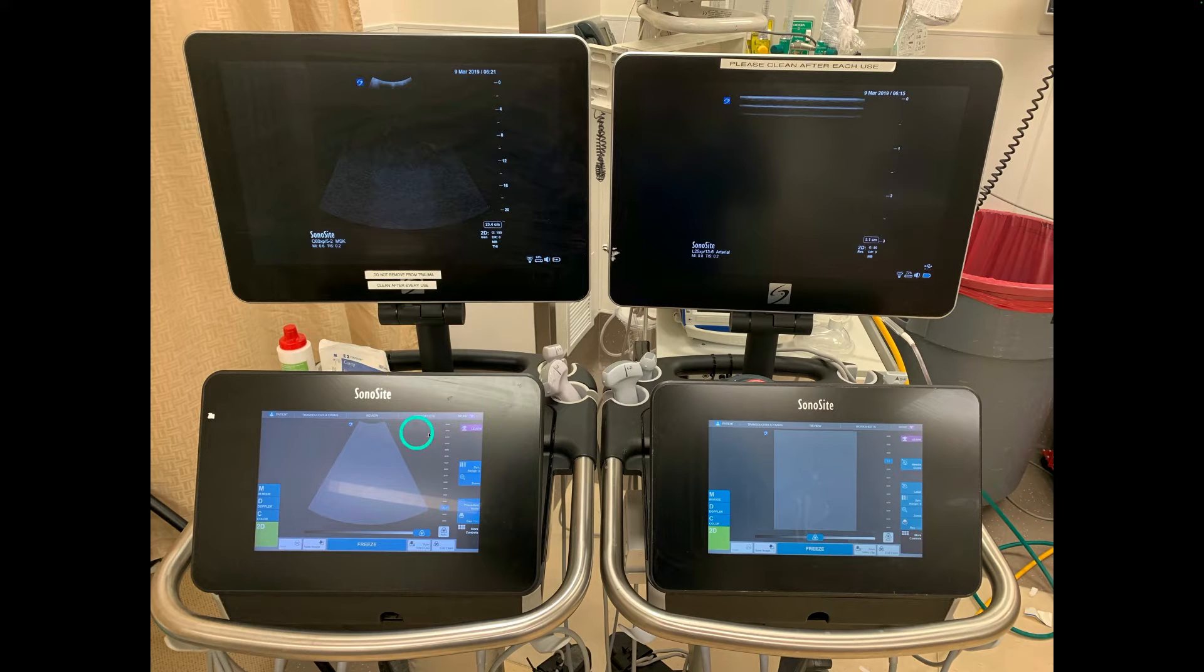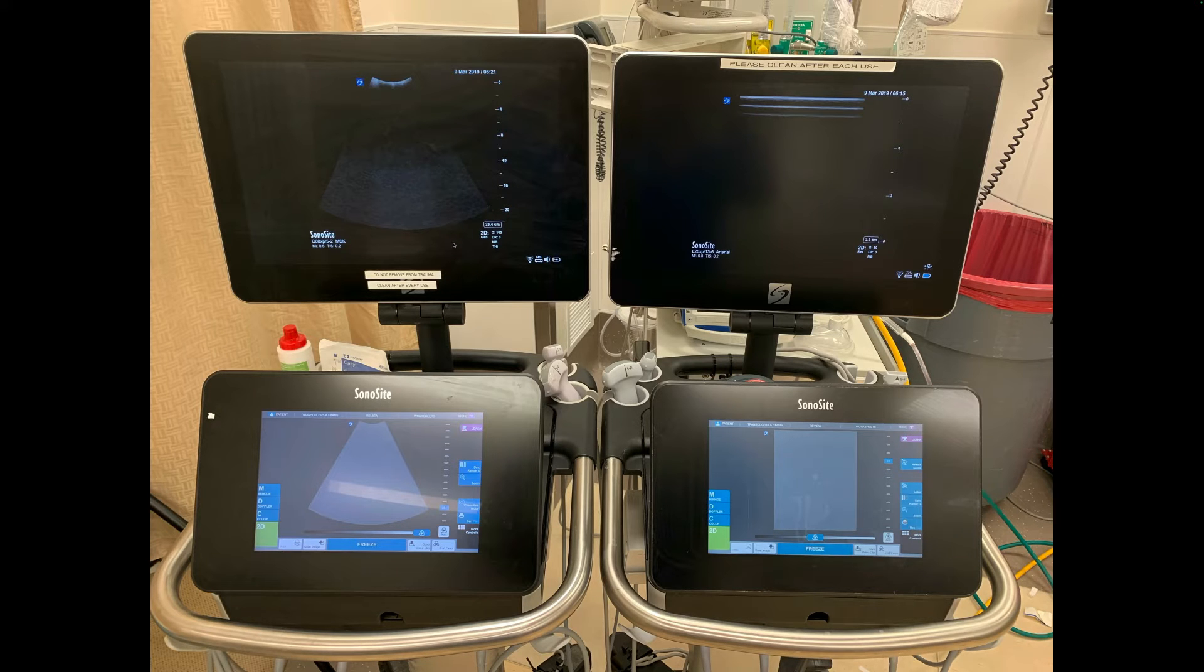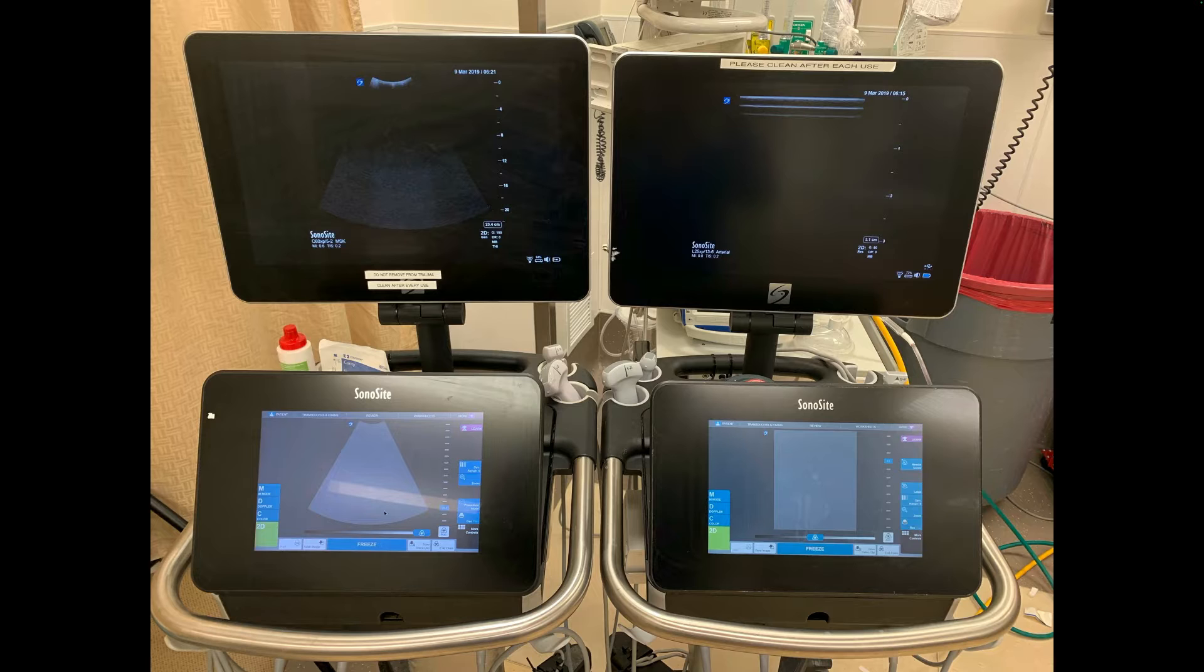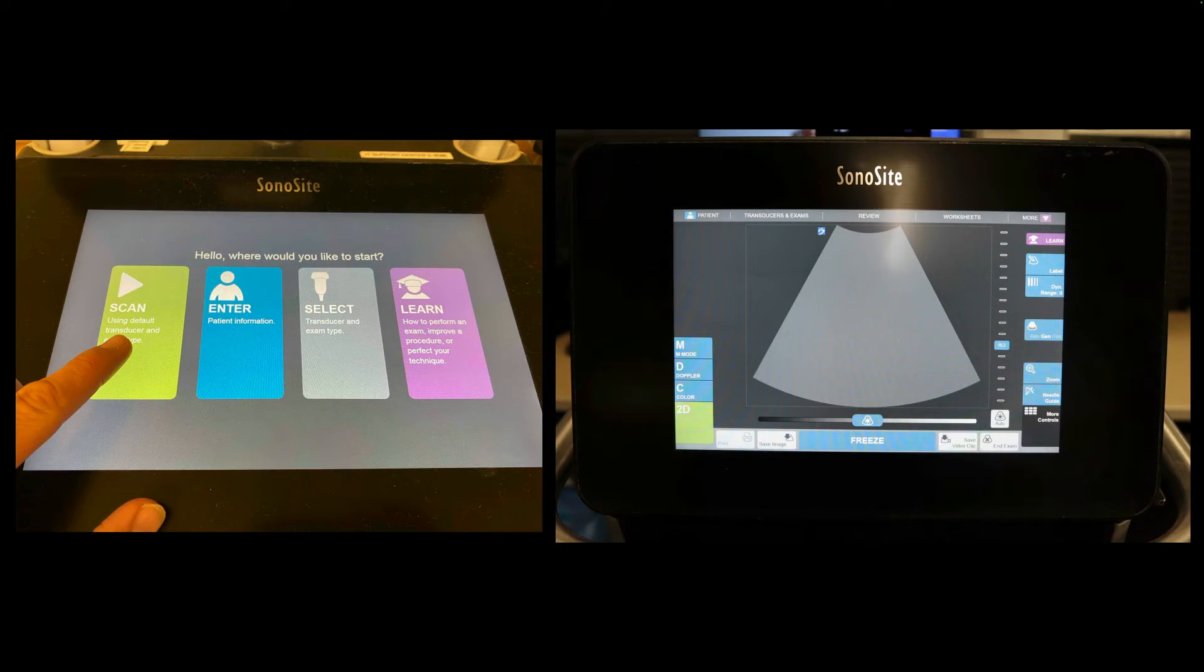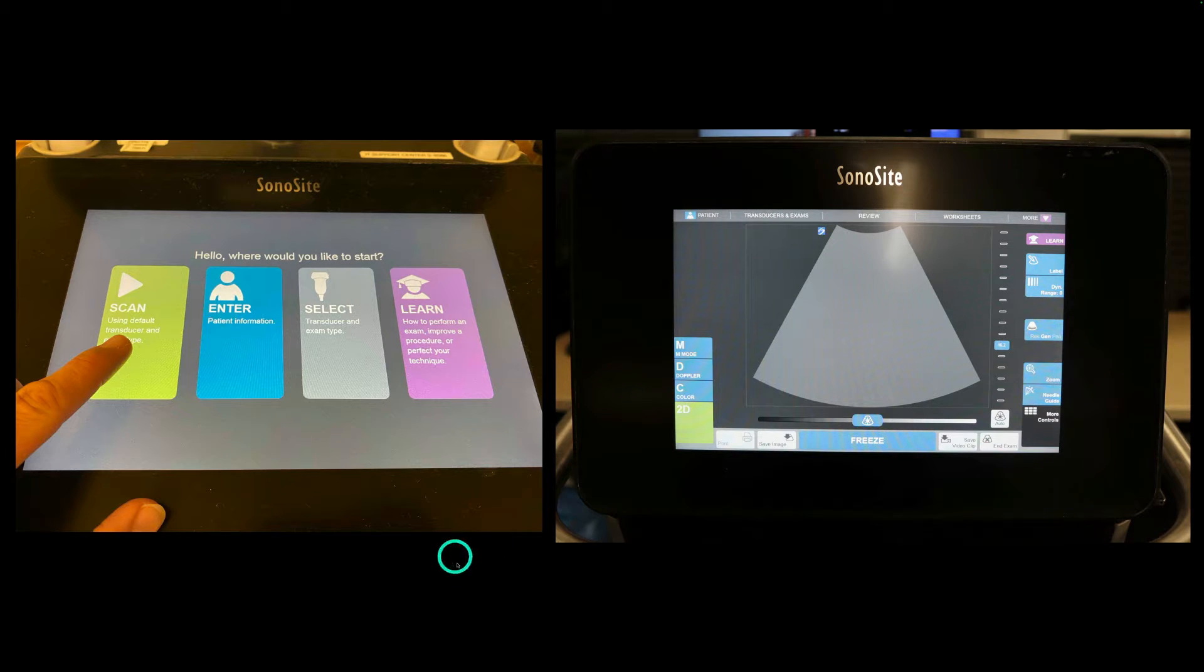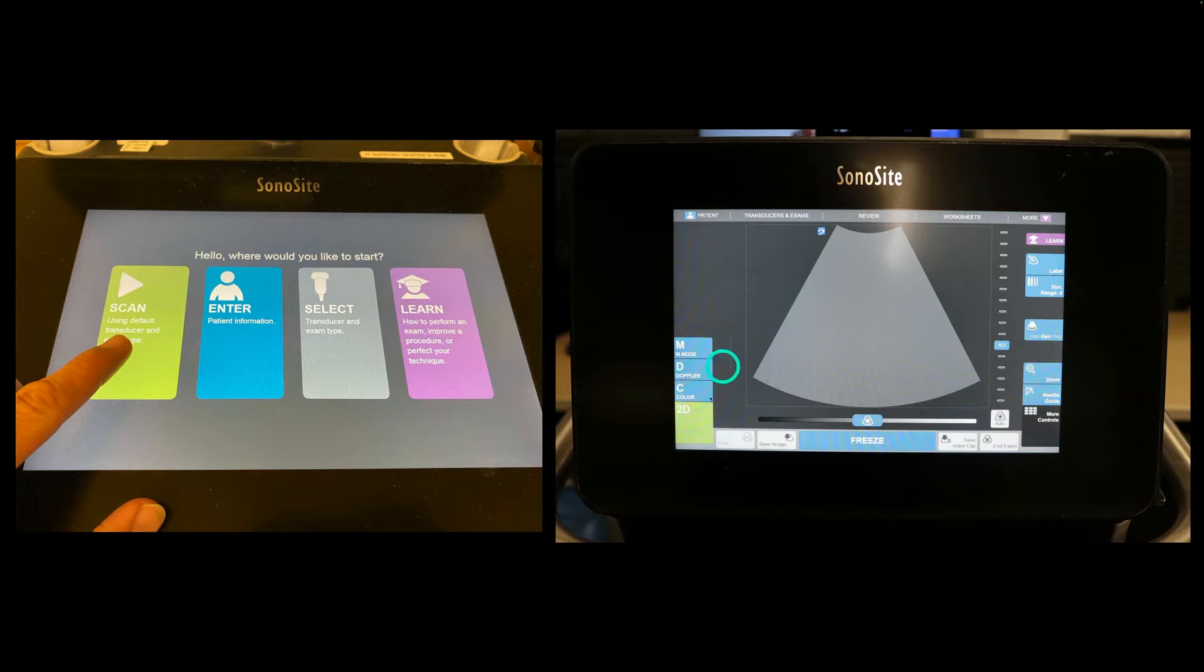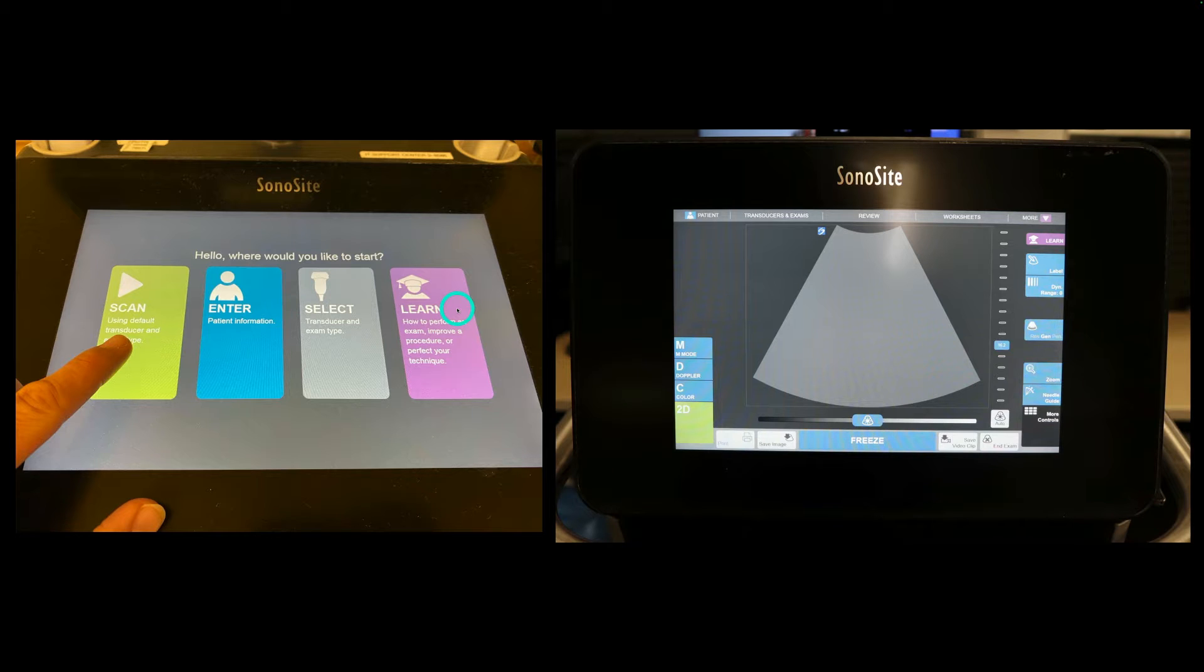Now this right here, this is touchscreen. This is not. I personally often get quite confused by that at times. Now let's talk about what to do with this screen down here, how to enter patient data on the screen, and then how to select the appropriate transducers. You might get this bottom screen in two different kinds of orientations. This is the ready to scan screen, and this is the more kind of starting out screen.